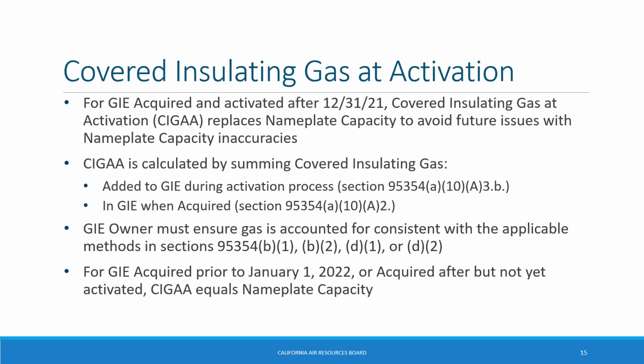Every GIE device has a capacity, which is the amount of covered insulating gas that it is designed to contain while operating. Under the original regulation, the capacity of each device was established by the manufacturer, typically on the nameplate. CARB staff heard from stakeholders that the capacity specified on manufacturer nameplates may be inaccurate. Therefore, under the amended regulation, the capacity of GIE acquired and activated after December 31st of 2021 will be determined using a new method, so-called covered insulating gas at activation, or CIGA. CIGA is calculated by summing the amount of gas added to a device during the activation process and the amount inside the device when it was acquired.